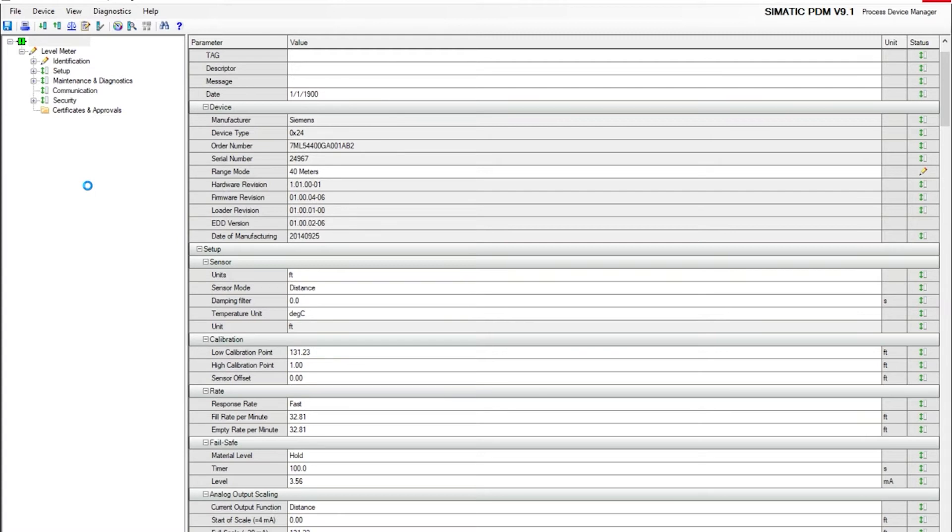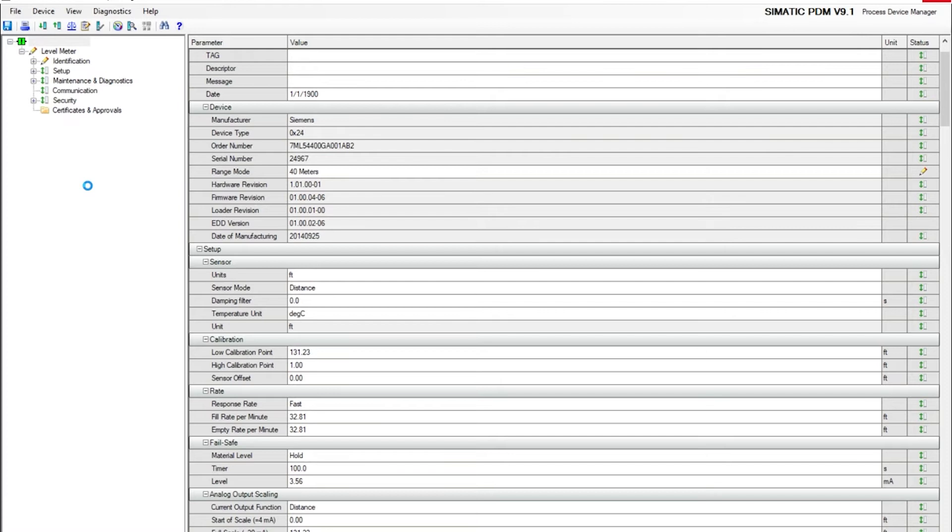When do you want to do manual TVT shaping? In some applications, you will have some obstructions such as supporting beams, pipes, ladders, and even in some cases you will have some false echoes. Manual TVT shaping can ignore those obstructions or echoes.